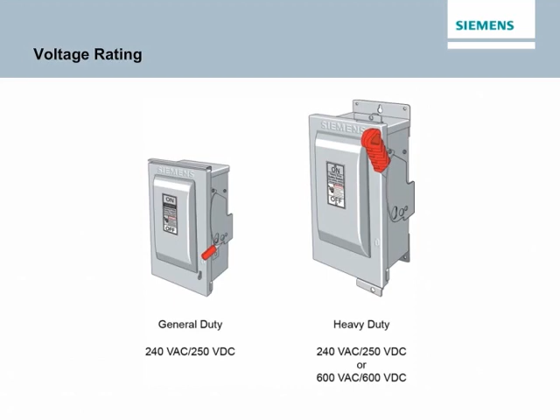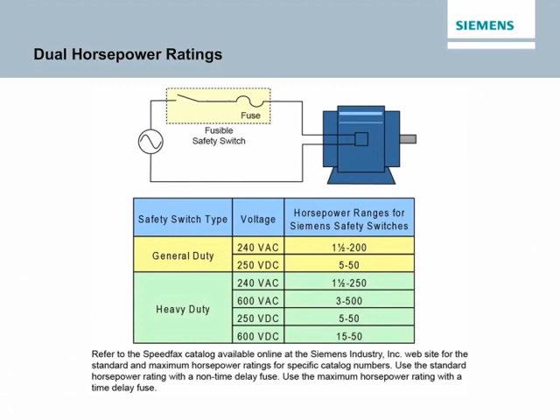Siemens safety switches have 2 horsepower ratings for motor applications. This is referred to as dual horsepower rated. For example, a switch might have a standard rating of 10 horsepower and a maximum rating of 30 horsepower. The standard rating, 10 horsepower, applies when non-time delay fuses are used. The maximum rating of 30 horsepower applies when time delay fuses are used. The accompanying chart reflects the range of horsepower ratings for Siemens safety switches.